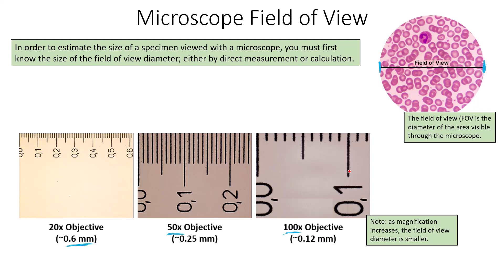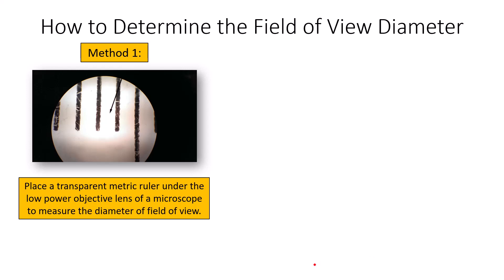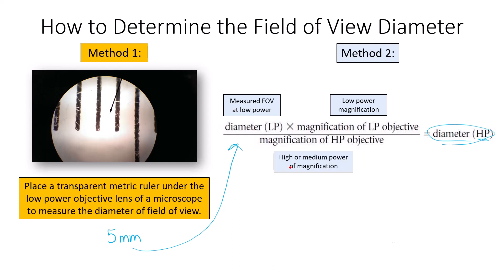There are two methods to determine the field of view diameter. Method one: place a transparent metric ruler under the low-power objective and physically measure the diameter — for example, counting millimeter marks to get a measurement like 5 mm. Method two: use an equation where the low-power measured diameter and low-power magnification are used to calculate the diameter at higher magnifications.